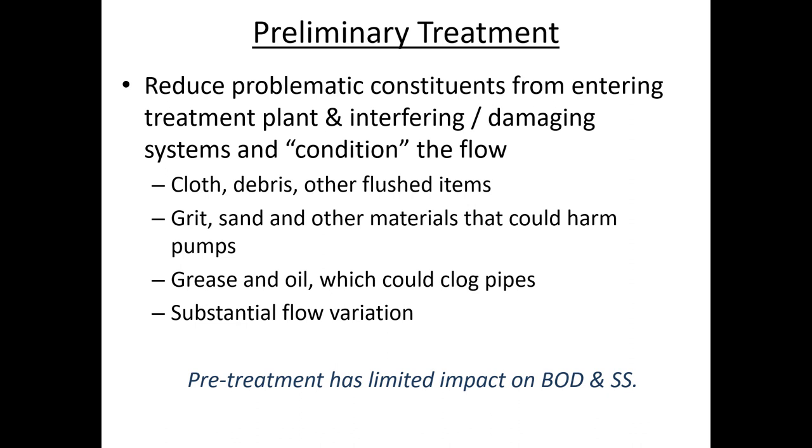The one sort of asterisk or exception to that is there are a few limited cases where we aerate either a grit chamber or flow equalization basin. And depending on how long the water stays inside of the flow equalization basin, it could reduce the BOD a little bit, but not a lot, because flow equalization basins don't have activated sludge, and so it's just the natural process of waste being broken down. And so it doesn't have a real significant reduction in BOD.